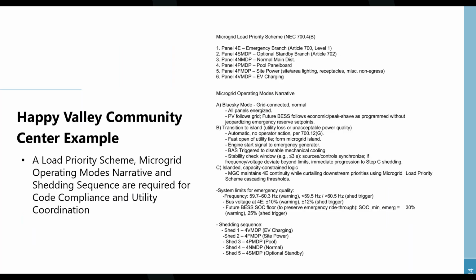Once you're in islanded mode, the load priority scheme activates, and under that load priority scheme is the shedding sequence. In this case, EV charging gets shed first, then site power, which is sports field lighting in this specific building and a significant load, then the pool, then normal power in the building, and finally optional standby. This sequence is in place so the system can manage the loads on the building's switchboard.